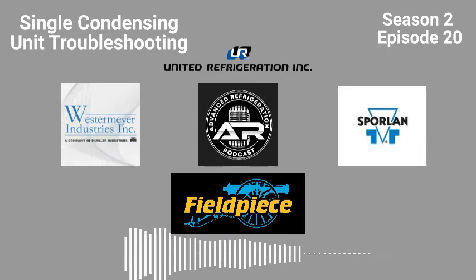We have that issue at Aldi with the CO2 stores. I'm like the meat coils. It has one of the smallest Danfoss pulse valves in it, and it'll pulse for like 2 seconds and it floods out. But what I'm saying is I think that the condensing unit being so oversized is increasing the TD on the coils, like you said, and it's undersizing the pulse valves to the point where they're already undersized to begin with, probably.